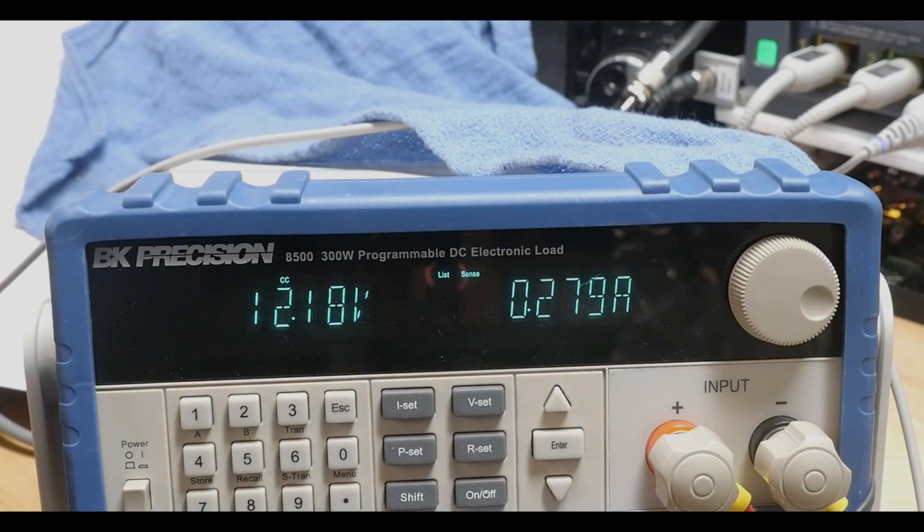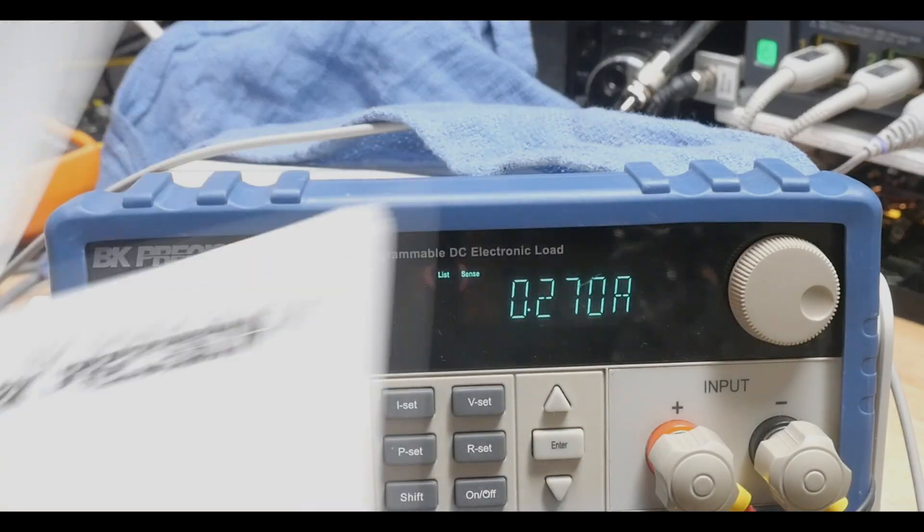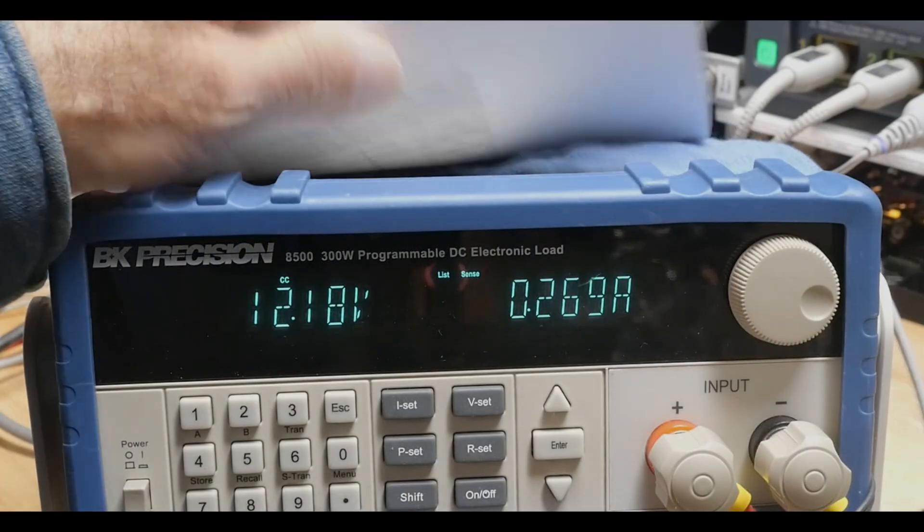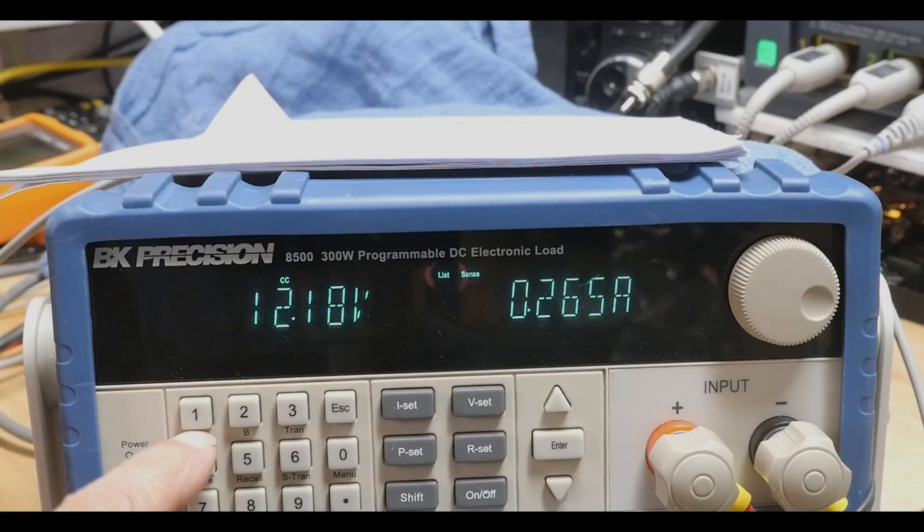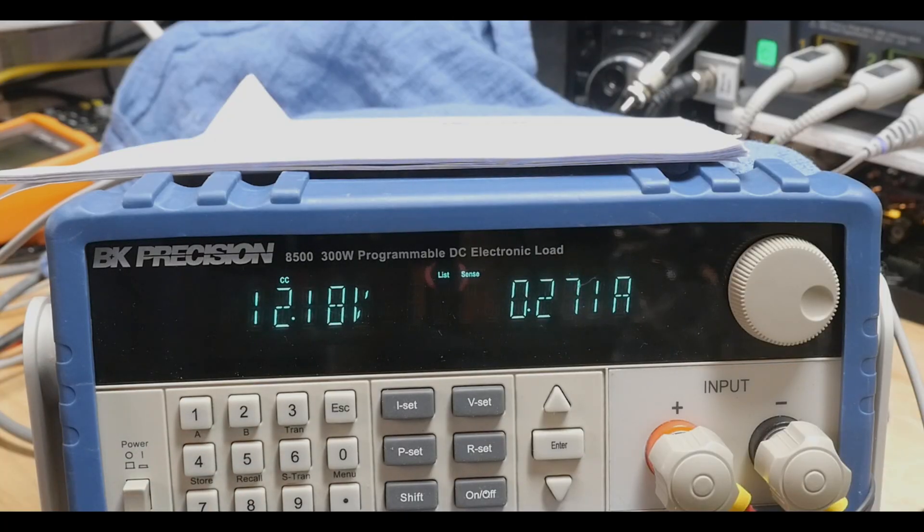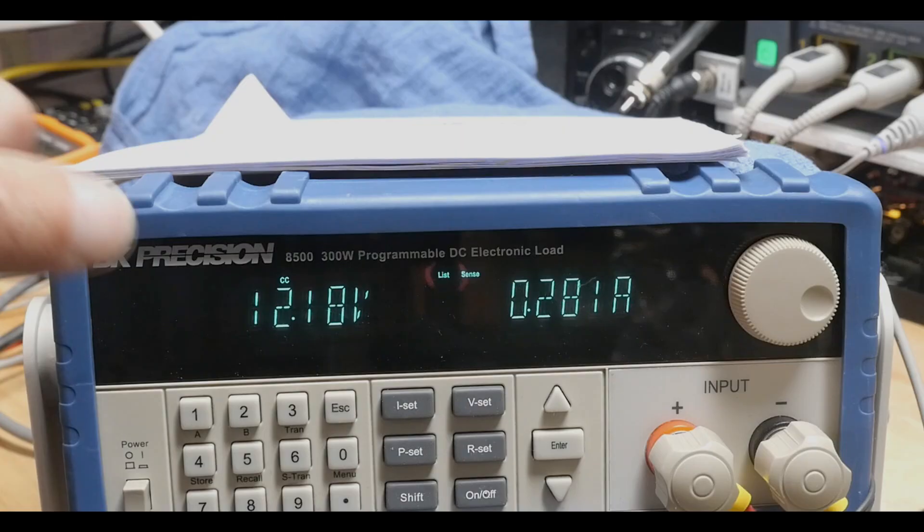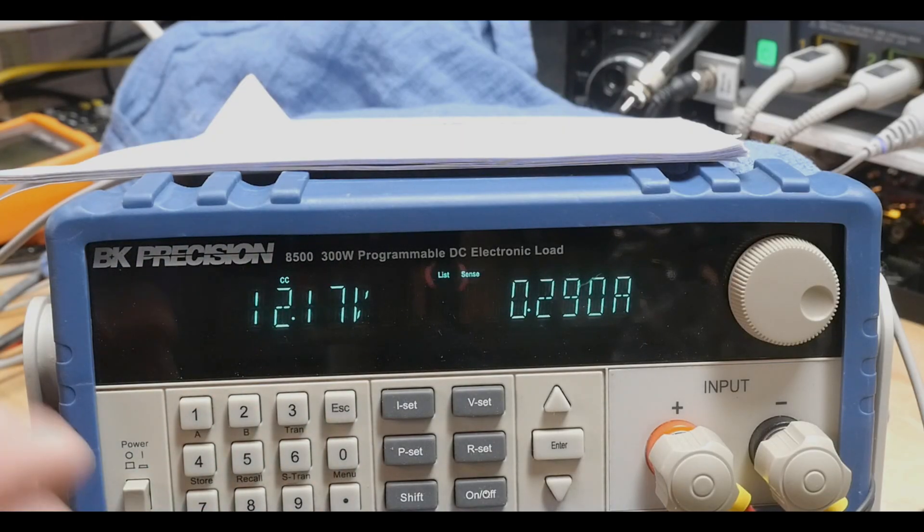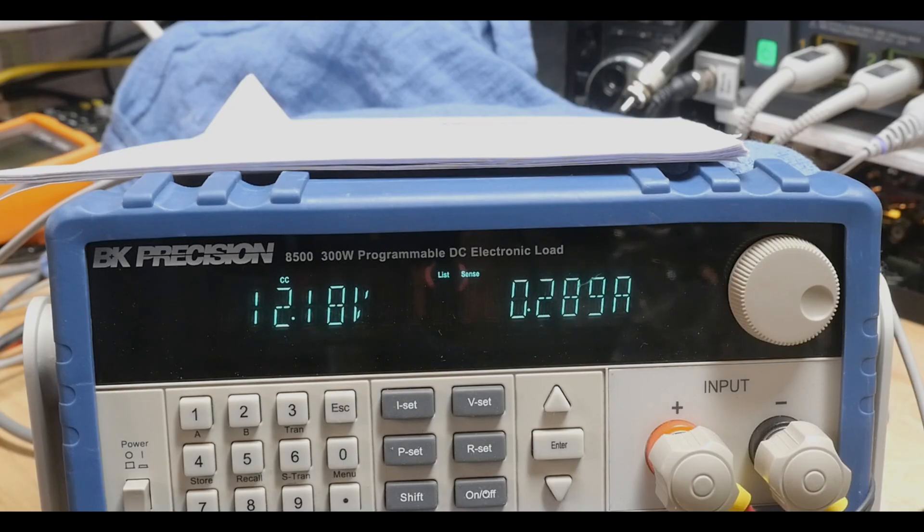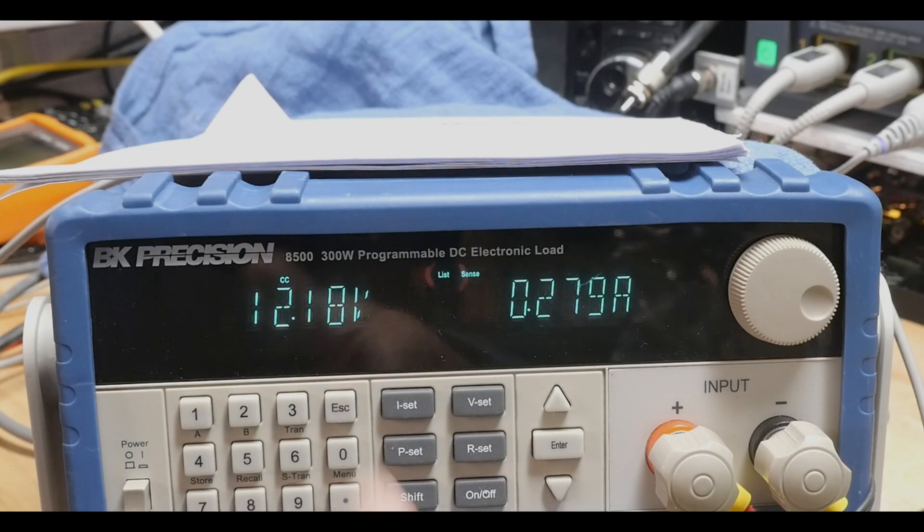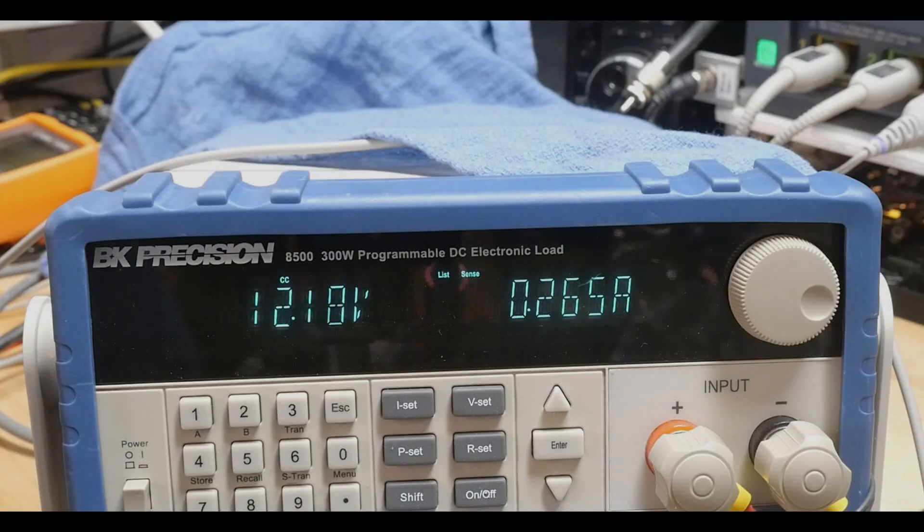This machine has another way of doing it. I'm not going to demo it, I'm just going to talk about it. There's actually an A setting and a B setting. You can set two levels and then it'll just pop up and down between those two levels. So it's an easier way to do a quick transient response instead of going through and creating a list.